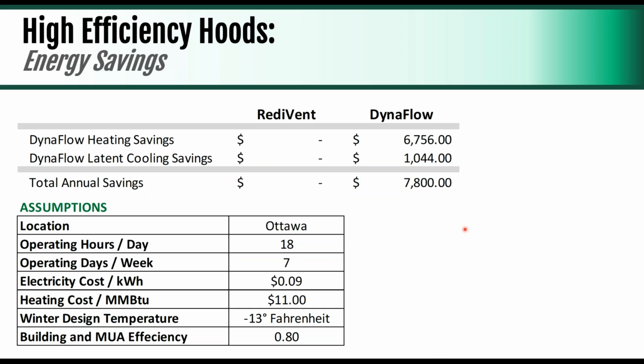One of the things that we like to get from people as we're designing projects is all of the assumptions. We state these in everything so that everyone can poke, prod, question, change them if they want. But we got location. We use the ASHRAE data to populate degree days and everything based on that. Then operating hours, days a week, electricity costs, heating costs per million BTU, design temperature, and then the makeup air efficiency. So that's where we get everything.